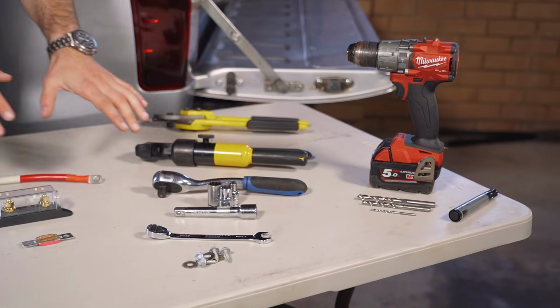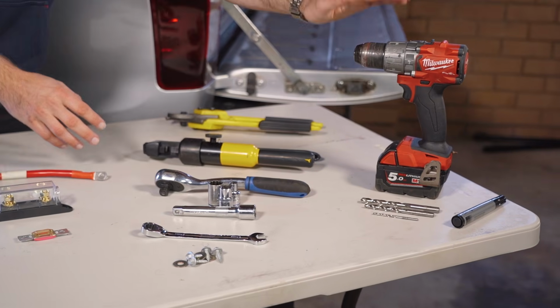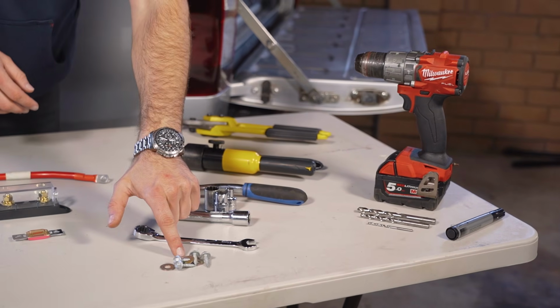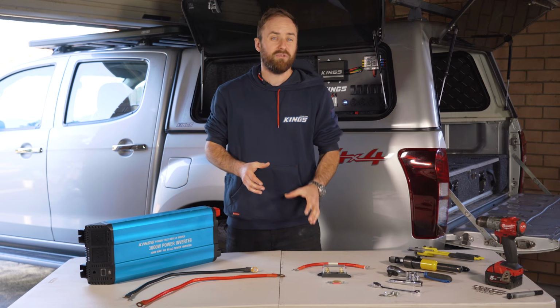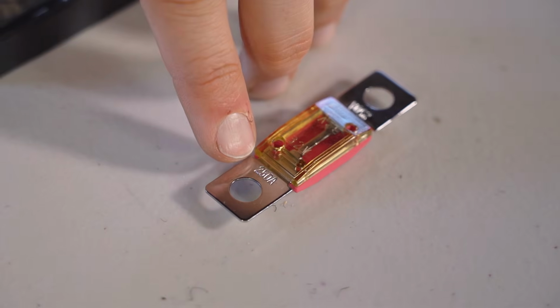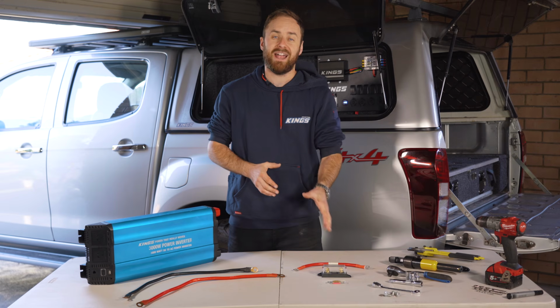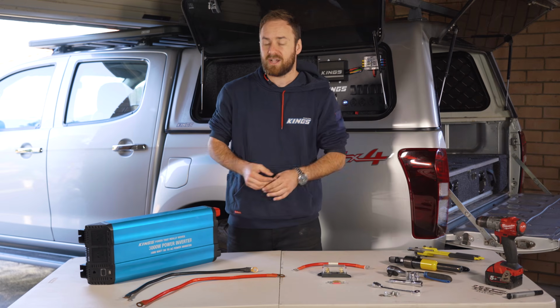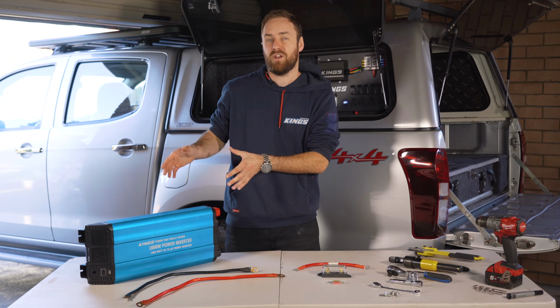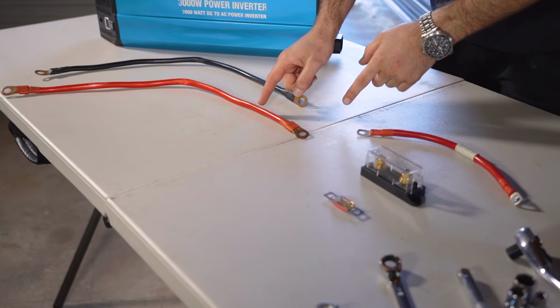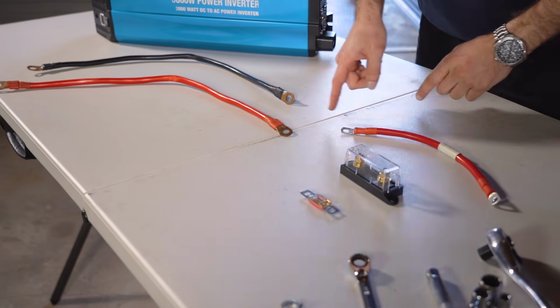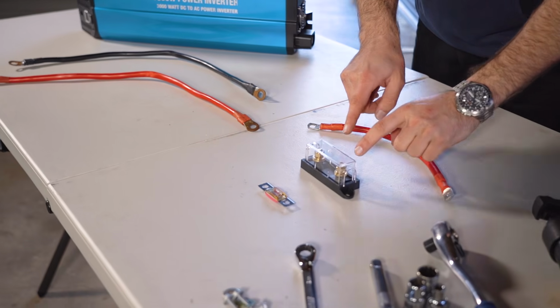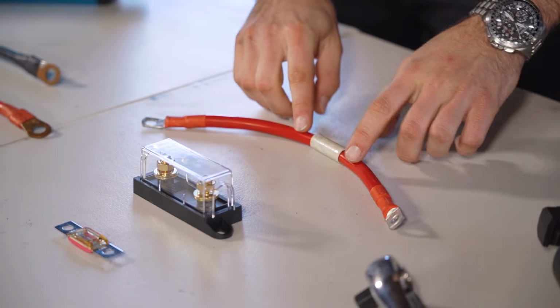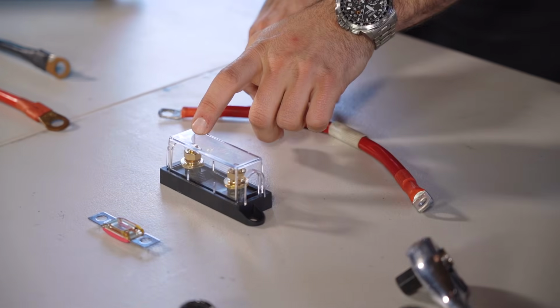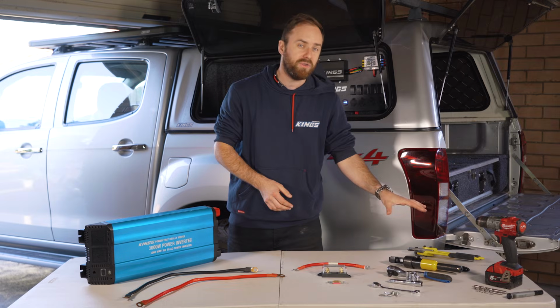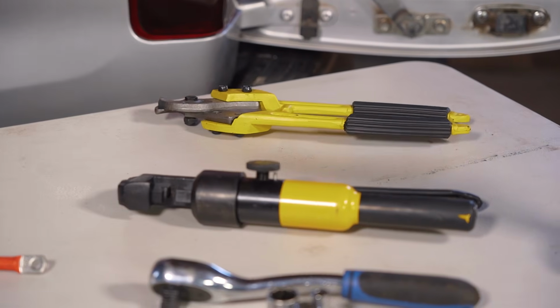You'll also need some basic tools to install the unit and some way of actually mounting the inverter. I also recommend that you run at least a 250 amp fuse or circuit breaker, and you could use a 300 amp circuit breaker if you're intending to use your inverter at its upper limit. Now, if you're adding a fuse, you'll either need to cut the included wiring and add terminals to fit the fuse holder or circuit breaker, or you'll need to add an extra piece of wiring to connect it all up. So you might also need some 12 volt tools as well.